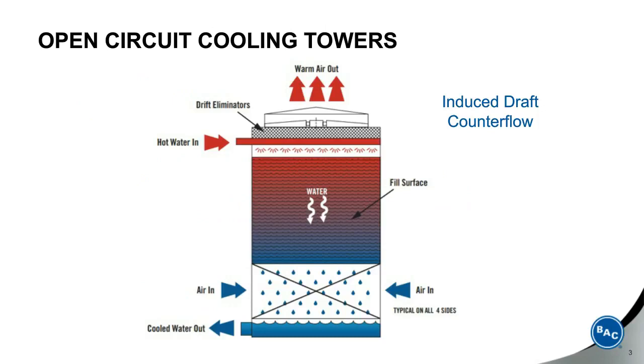Thank you, Andrew, and welcome everyone to our webinar. Let's first talk about open-loop cooling systems. And of course, what we're talking about there are open circuit cooling towers. They come in a variety of sizes and shapes and designs. And what we start off with here is an induced draft counterflow unit. What you see here at the bottom is the water which goes out to the load to be cooled, returns warm or hot, and is sprayed over what is called a fill deck or heat transfer surface. Air is induced up through the cooling tower where the water and air mix and the water is cooled before returning back to the system load.